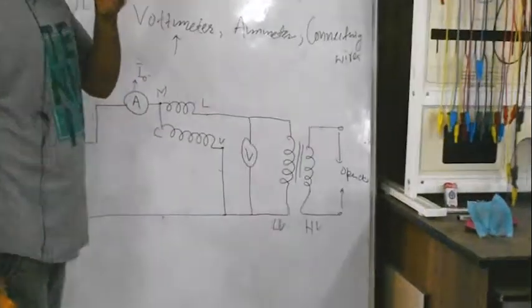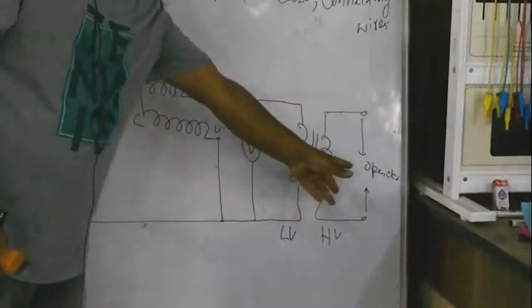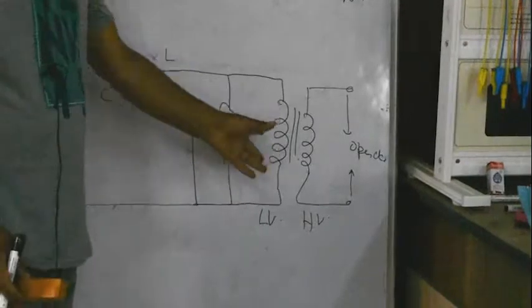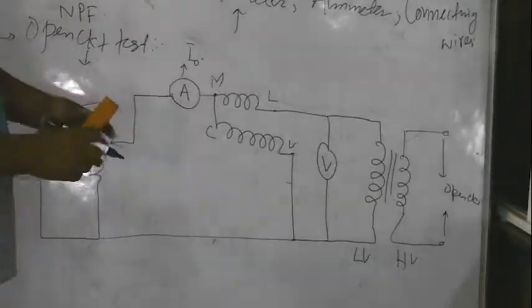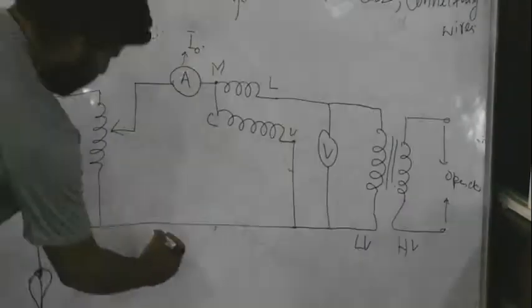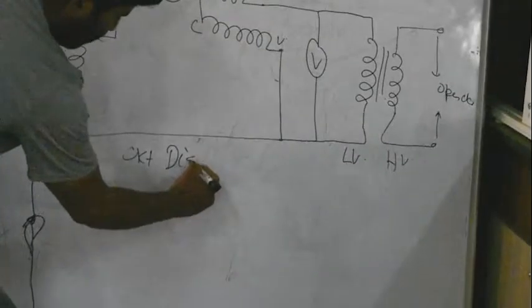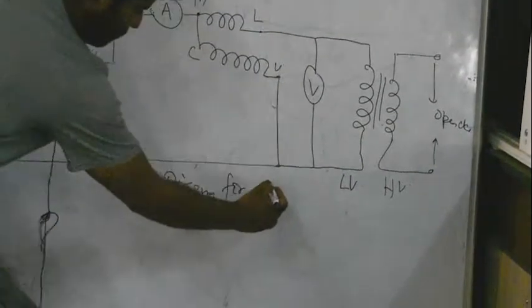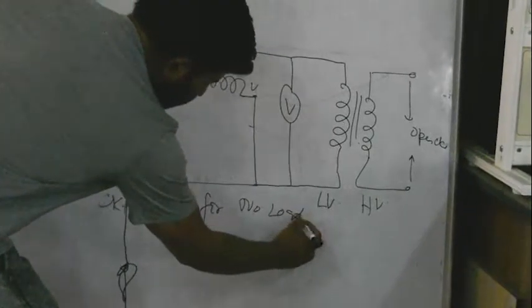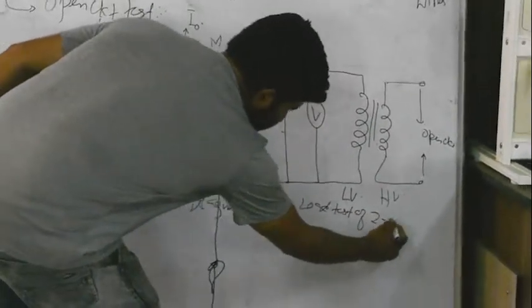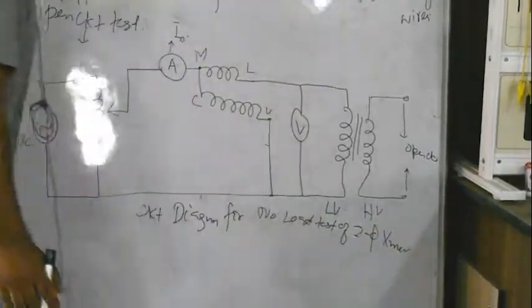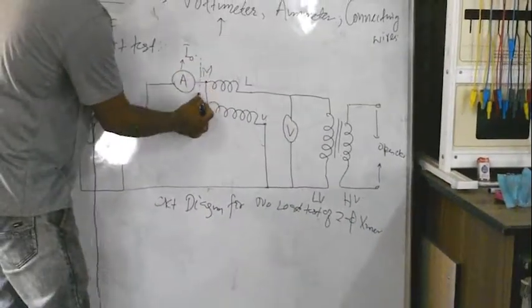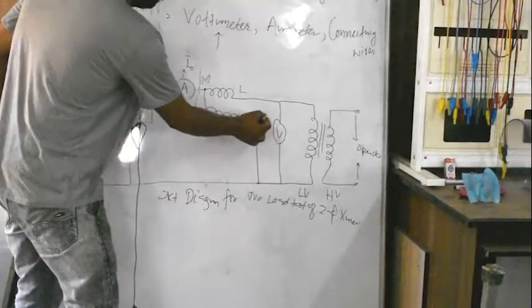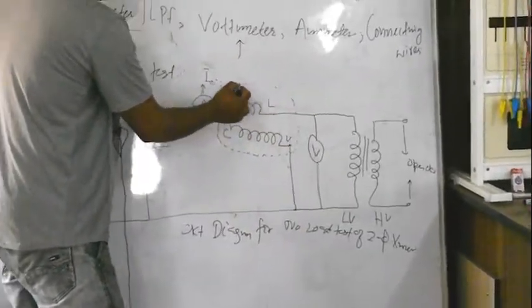Say for example this is the high voltage side. So the high voltage side is open circuited, and only the primary side, or the low voltage side, is energized by a varying AC power supply. So now, as seen from the circuit diagram, this is the circuit diagram for the no load test of a single phase transformer. Now as seen from the circuit diagram, we have 3 measuring equipments. That means we will be having 3 readings.